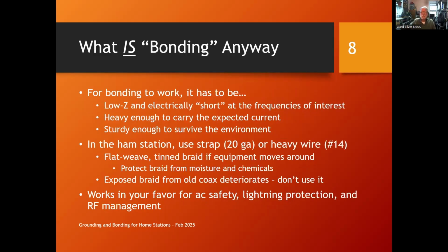So for bonding to work, it has to be low impedance. You don't want impedance in your bonding conductors, because if you have current flowing in that bonding conductor, it'll cause a voltage drop, and you don't want voltage drops. So your bonding conductors have to be as low impedance as possible, and electrically short so that it doesn't start acting like a transmission line.